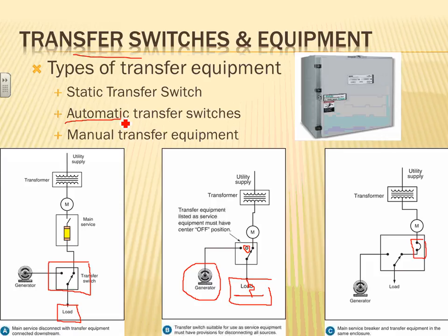And with the auto transfer switches, there are two options. You can have open transition or closed transition. Open transition interrupts the flow of power to the building, and then you connect to the generator. That's your open transition, where you see a blip in the system. In closed transition, you connect the two systems together, generator and utility, and then together they're both looking at the load, and then you drop the utility. The difference is you wouldn't see a blip in the system, so you wouldn't see the light turning off. Either one of them will meet the requirement of the auto transfer switch.